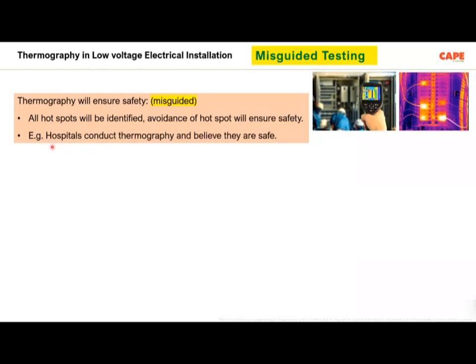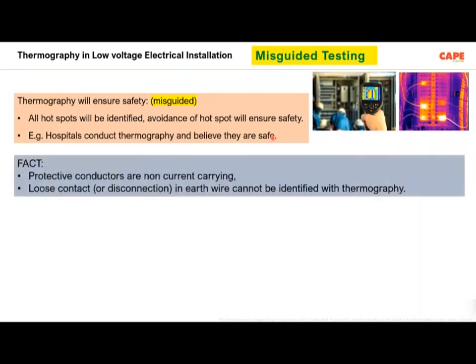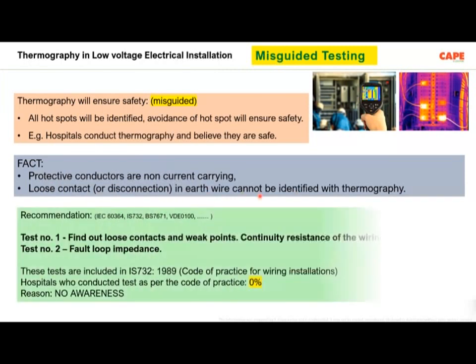But as I said, for example, hospitals conduct thermography and believe they are safe. Last year, after the fire accident, I was visiting some of the hospitals and I asked them how they are ensuring safety. Then the reply is, no, we did thermography and we do thermography every 2 years to ensure safety. But when I asked what about your fundamental testing, in fact, they were never aware of it. So the fact is, protective conductors are non-current carrying. Loose contacts in an earth wire cannot be identified with thermography.